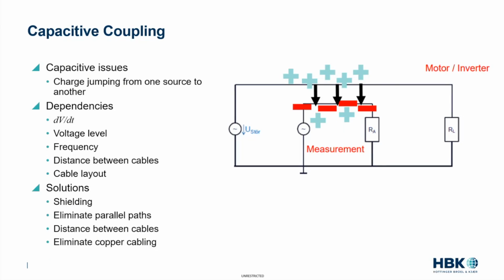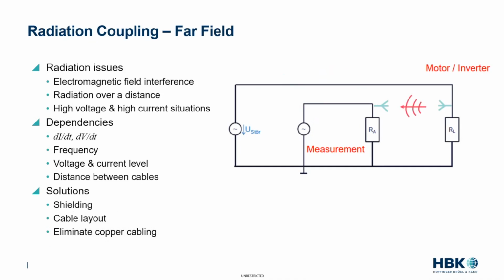So capacitive coupling. With capacitive issues, we've got charge jumping from one source to another. We've got dependencies, of course, on dv/dt, the voltage level, the frequency, the distance between the cables, and the layout of your cables. So again, solutions include shielding, eliminating parallel paths, distance between cables, and also trying to eliminate copper cabling. And we'll talk again more about these solutions in a few moments. And then there's also radiation coupling. Electromagnetic field interference, radiation over a distance, in high voltage and high current situations.